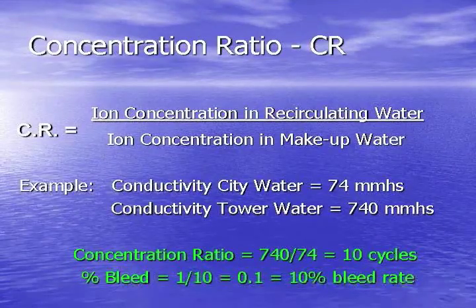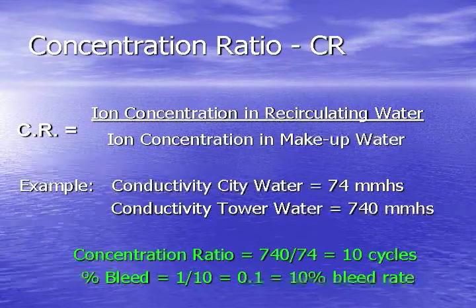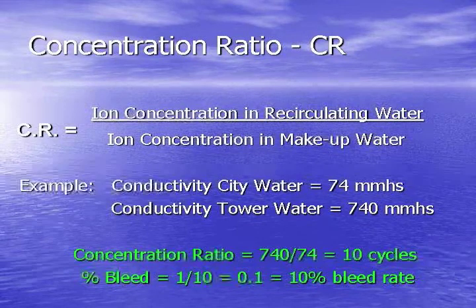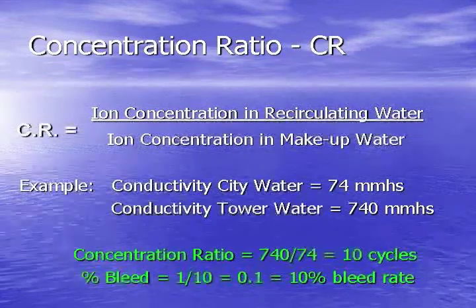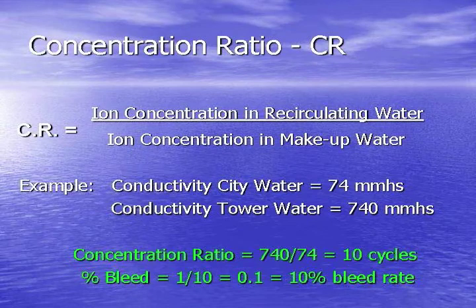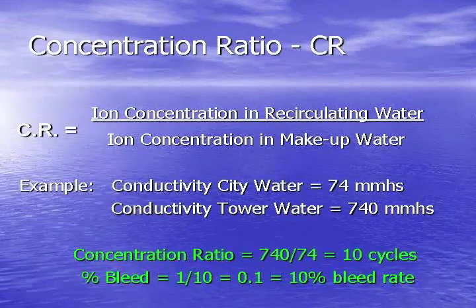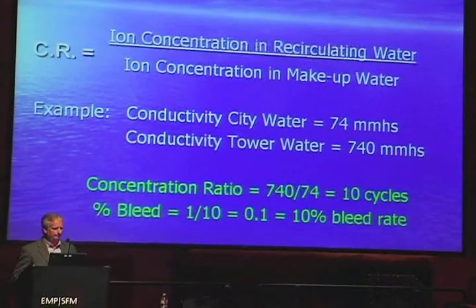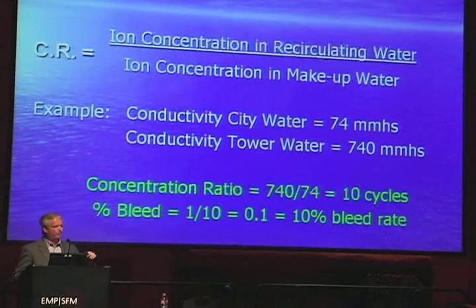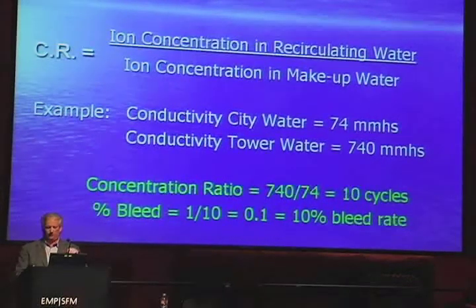So the definition of concentration ratio is basically the ion concentration in the recirculating water divided by the ion concentration of the makeup water. That determines your cycles. For example, the conductivity of city water here is about 74 micromhos. If your tower runs 740 micromhos, so you're concentrating it up, you're running basically 10 cycles. 740 divided by 74 is 10 cycles. At 10 cycles, you're running about 10% bleed rate. So in other words, of all the water going to the cooling tower, about 10% is being removed through bleed. The higher you go, the smaller percentage your bleed rate. Obviously, the lower you go, the higher percentage your bleed rate.